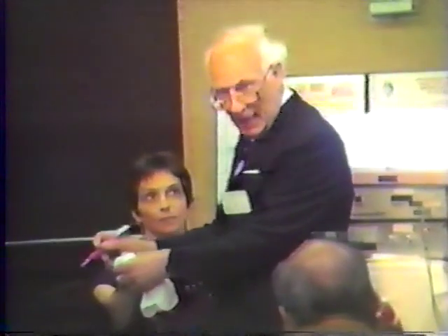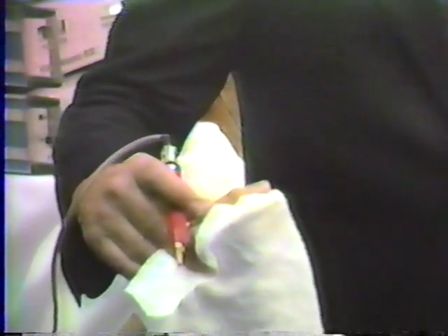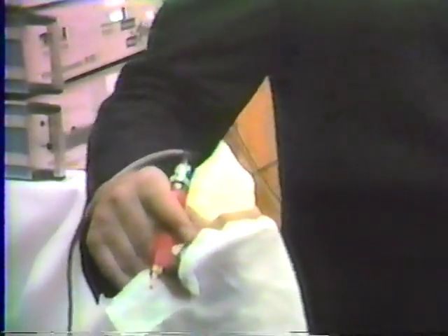If you have your hand free like this, it doesn't work. I can't measure in this way either. It's not possible. I have to support my hands in a very careful way, with some cloth between, to make sure that as little current as possible is transferred upon the patient or upon myself.